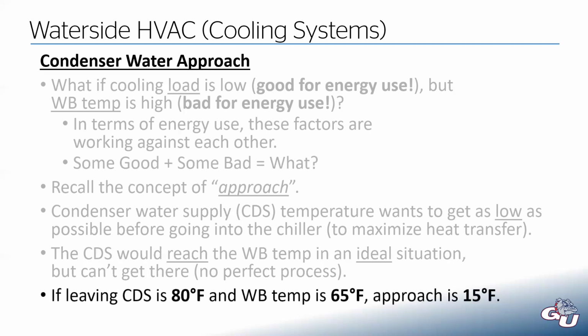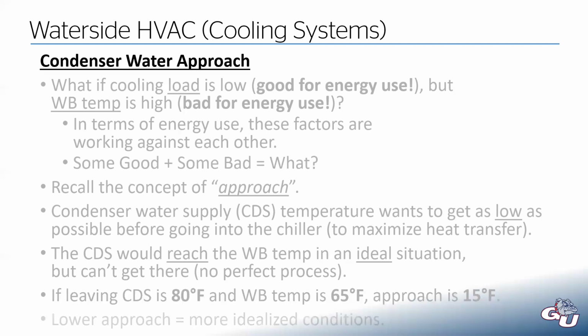As an example, if our condenser supply is 80 degrees, which if you think back to that diagram I showed you, that's what I used in that example, I think. If our condenser supply is 80 and our wet bulb temperature is 65, our approach there is 15 degrees. We got within 15 degrees of ideal heat transfer. So a lower approach means we're approaching those idealized conditions. Same idea as approach when we're talking about an air conditioning system.